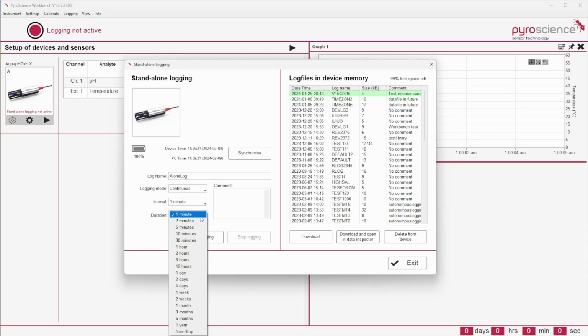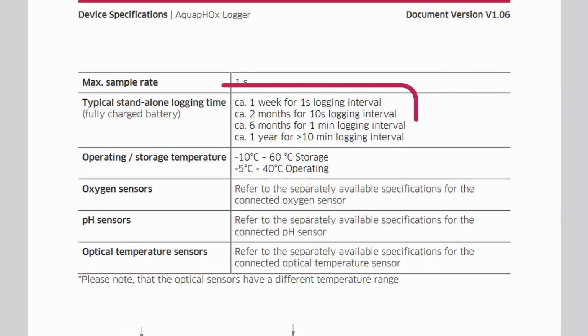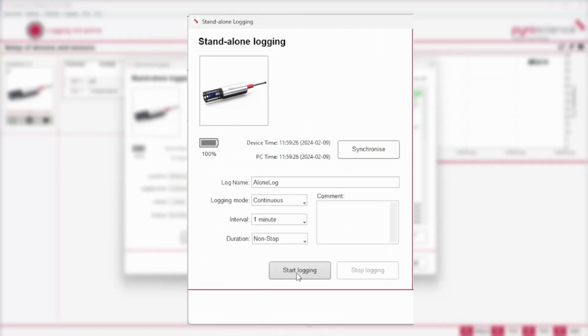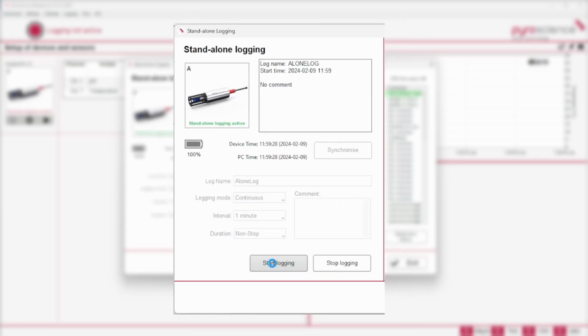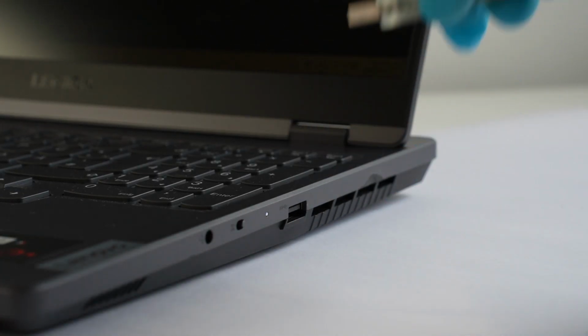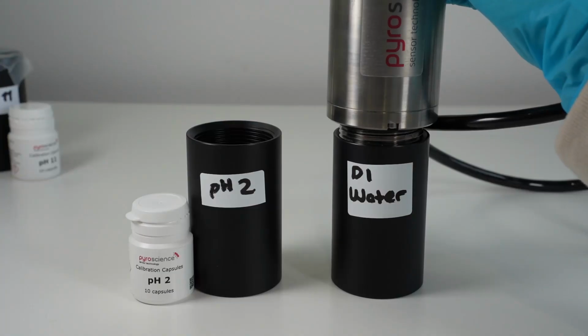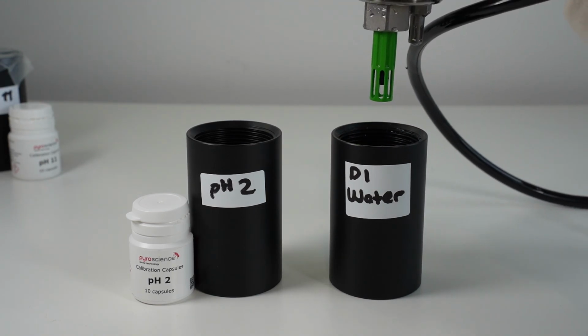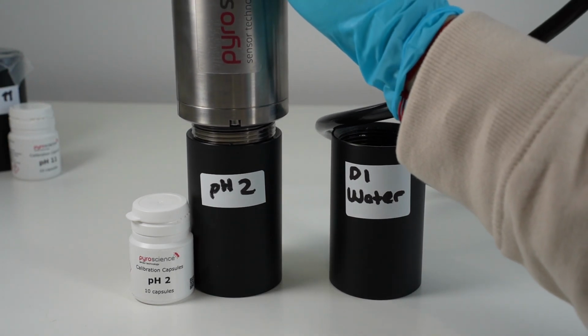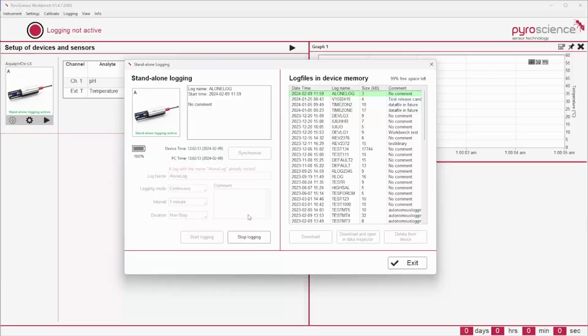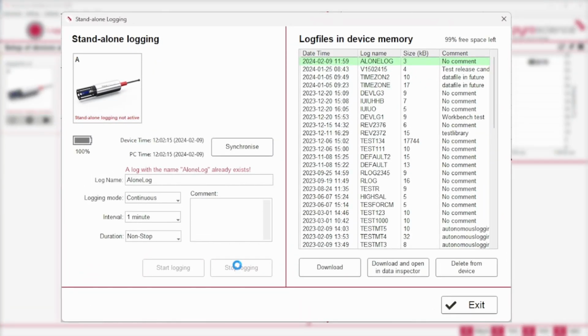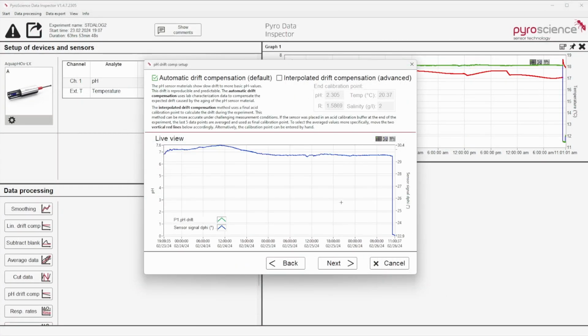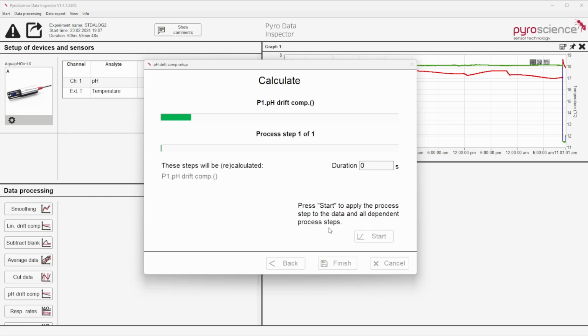The typical standalone logging time for a fully charged battery is around 6 months for 1 minute logging. This time can be extended with a longer logging interval. Start the logging by clicking on Start Logging. The device can now be disconnected from the PC and will continue logging the data. After deployment, it is important to place the logger for 5 to 10 minutes in freshly prepared pH 2 calibration solution before stopping the logging. This data can be used to automatically compensate the pH drift via the Pyro Data Inspector software.